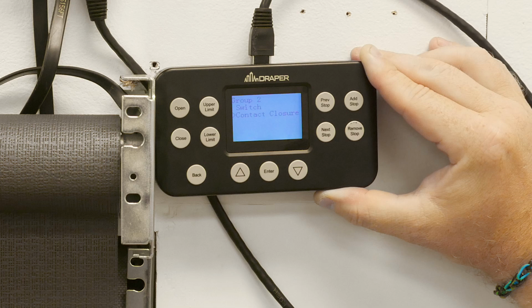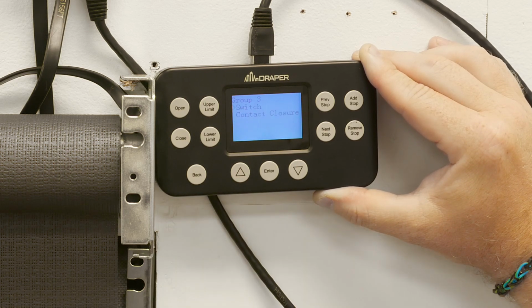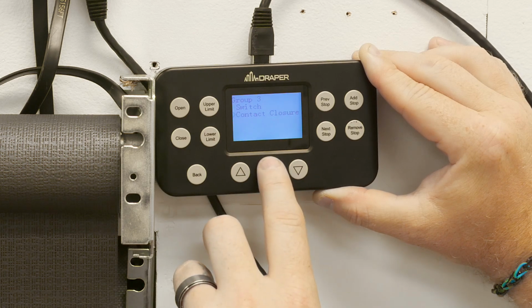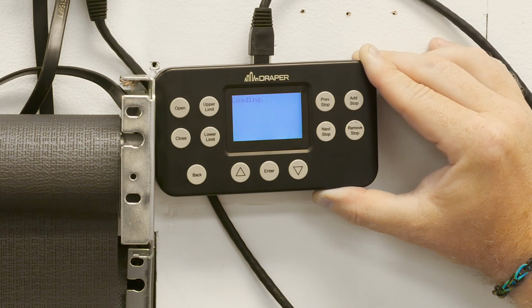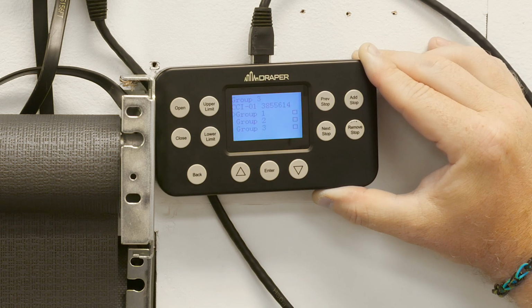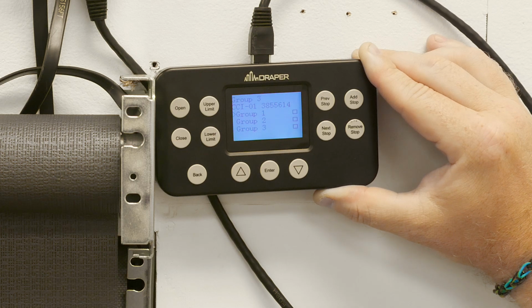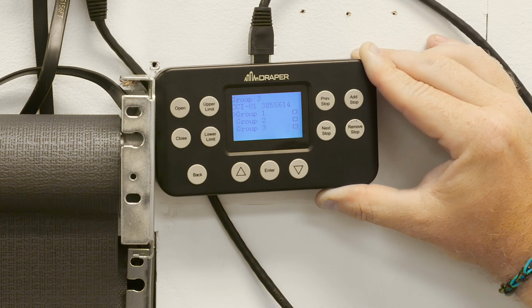Same principle is going to apply for the contact closure interface. I'm going to select my group number, so I'm going to go back to my group devices menu. I'm going to navigate down to group 3. I'm going to select contact closure. This pops up, I only have one contact closure available, so I'm going to go ahead and check mark that box, hit enter. Now, once I select the contact closure interface, I see the 3 groups that are available to it because it has 3 dry contact terminals. I can pick from those 3, or I can select all 3 of those to be part of the group.